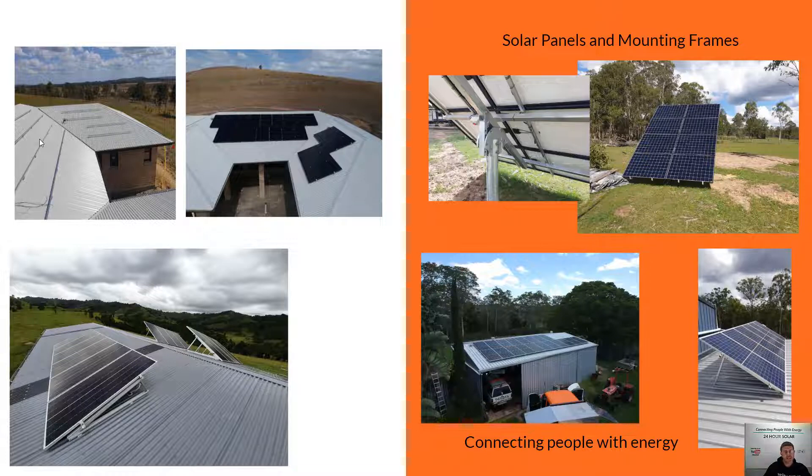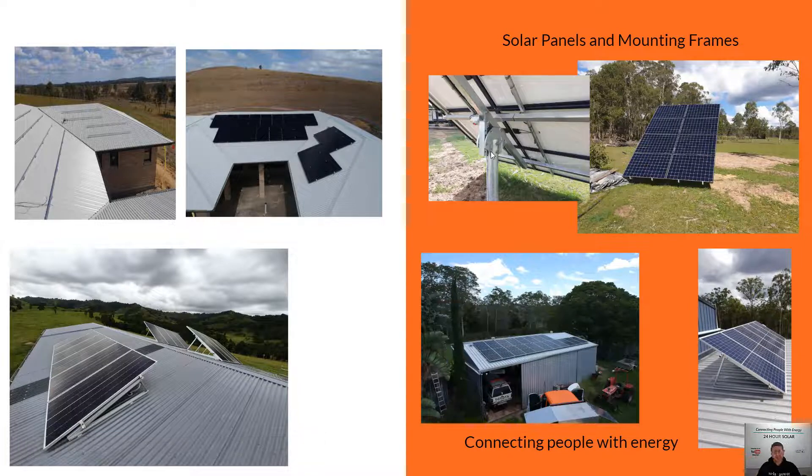You've got the option of mounting flat to roof. If you do have a flat roof, you can get solar tripods to mount your panels at the right angles. These can be adjustable over the seasons, though it's not really worth the effort to get up and adjust them. If you really want the ability to adjust your solar panels and make things easier over time, you're best getting a post mount or a ground mount solar system. The post mounts are adjustable so you can adjust them with the seasons, and it makes your life easier to clean your panels.